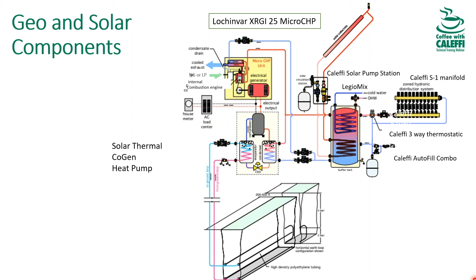One of the things that struck a chord as you were going through here, I was visiting a manufacturer over in Germany years ago when we were shopping out some solar components. I visited two different ones, and both had little cogens. It seems pretty common in some of the small manufacturing facilities over there. I remember one engineer saying the key to make these work is you've got to pull all the heat off that engine. A lot of them just take the cooling water temperature and use that, but he said you've got to put a girdle around the generator and pull that heat off. You've got to pull the heat out of the exhaust, pull the heat out of the cooling fluid, grab all that thermal energy - like you were saying all along, it's a thermal lead thing. So it's interesting to see how this unit was built, that they grab heat wherever they can off of that.